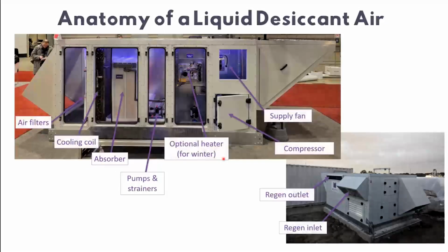So what does this hardware actually look like? Like I said, lots going on here. Conceptually, from a hardware standpoint, there's actually not a whole lot going on in the box. You have your outside air intake, and this could be a return air intake as well for recirc applications, a return air knockout if you're doing a mixed air application, or a bottom return 100% recirculation style application. You have a cooling coil, which you'll notice is not a particularly deep cooling coil because we're not doing all of our dehumidification with a DX system.